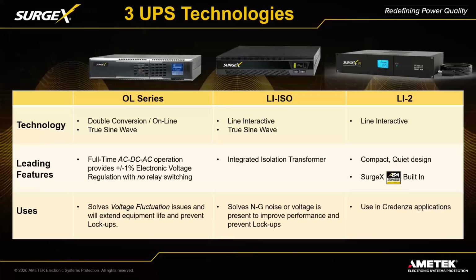And then we're scratching our heads going, well, we could have a loose neutral, we could have a missing ground, we could have another load tied together with that AV load you thought was dedicated. When those instances come up, sometimes I hear, hey, we want to go to the electrician, we want to go to the utility, and maybe we did, and it's going to take a while. I remember one integrator telling me it was going to take 6 months for the local utility to fix an issue with a corroded transformer outside the building. So what do you do? The homeowner was like, hey, can you solve my problem right now? And of course we were able to do that. Back then it was with a retrofit of 2 large format UPSs installed in that job.